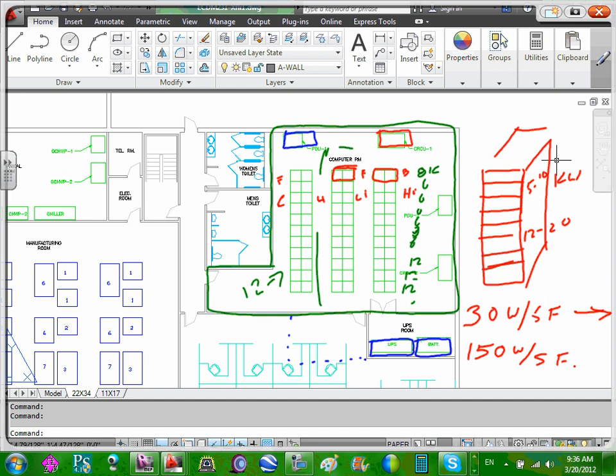I want to be able to give 150 watts a square foot on the floor, so we need to upsize my UPSs a little bit so they can handle that. How does this one get? I kind of misspoke. I'm reading the thing, 220 amp circuits with each server cabinet.